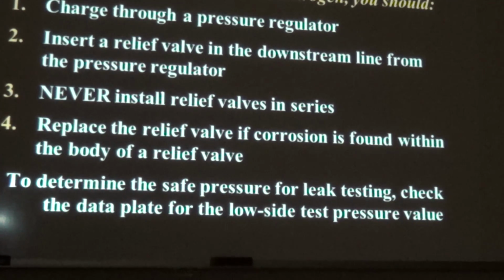Nitrogen pressure testing safety. When you're pressurizing a system with nitrogen, you should do four things. Charge through a pressure regulator, insert a relief valve in a downstream line from the pressure regulator, never install relief valves in series, and replace the relief valve if corrosion is found within the body of a relief valve. To determine the pressure that you're going to charge the system with the dry nitrogen to check for a leak, you're never going to exceed the low pressure operation number. So if it says that it's an R22 system and it's for air conditioning with a 40-degree coil, then it's going to say on the data plate that the low side pressure is 69 pounds PSI. You're not going to go over 69 pounds PSI for your pressure test.